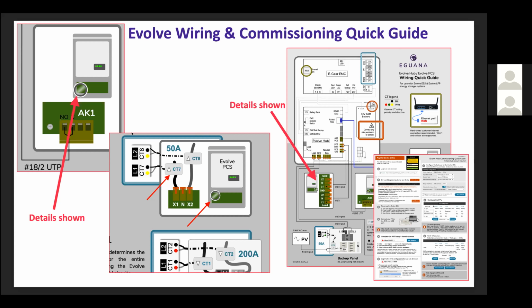The details are shown, for example, this is for the AK1 wiring, which is shown down in the lower middle section of the first page. The PCS cabinet, you know it's a PCS cabinet because it's got the lights on the front of it. That circle shows the detail of where that AK1 relay terminal plug is located and the wiring that would then connect to the Evolve hub, the AK1 PCS plug inside the hub. All of the other interconnections are shown similarly with the detail that's blown up on the left, shown in the small circle where it's located. CT placement, for example, here, as shown for the batteries inside the PCS cabinet, the little triangles show the arrow in which those CT arrows need to face. That's the end of the installation.